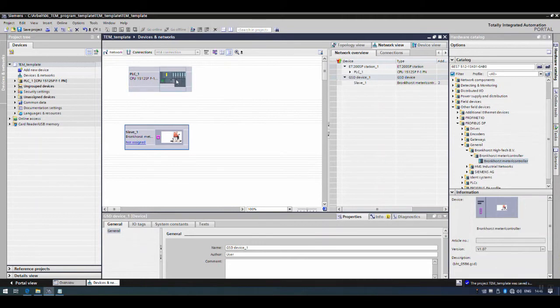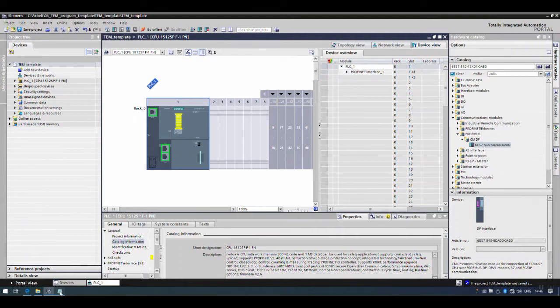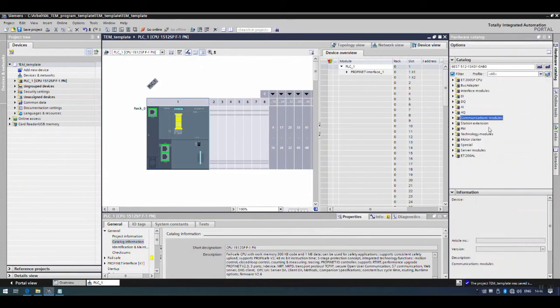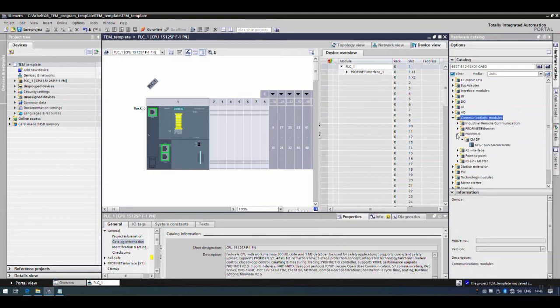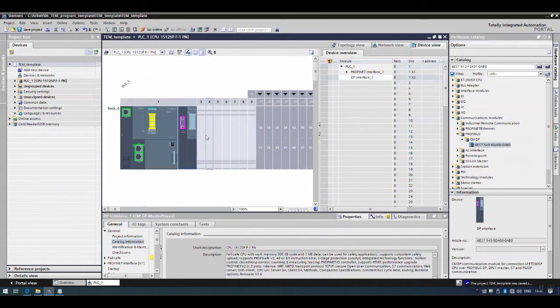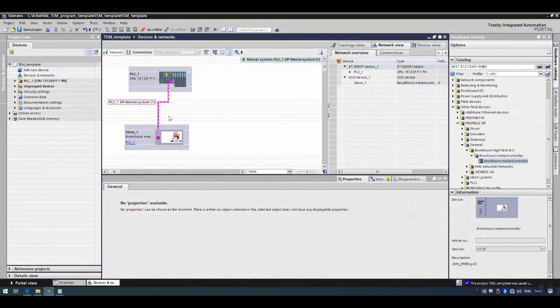As you can see, we don't have a PROFIBUS interface in this PLC — we need a PROFIBUS card to connect the PLC with the Bronkhorst MFC. The MFC is a slave so we need a PROFIBUS card as the master. Go to device view, find the communication modules, then PROFIBUS, and bring in the card. Now we can see it is connected to the Bronkhorst MFC and we have a PROFIBUS interface.